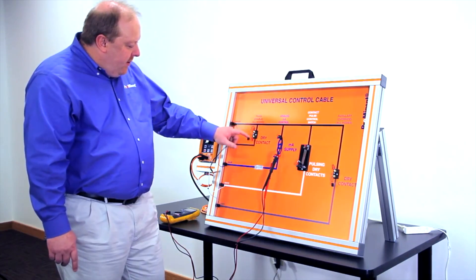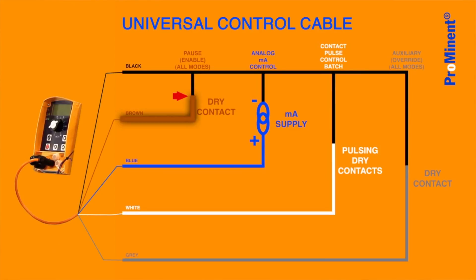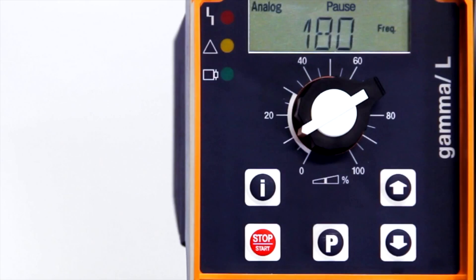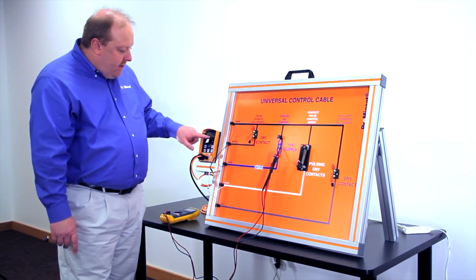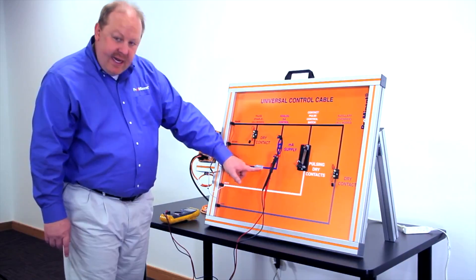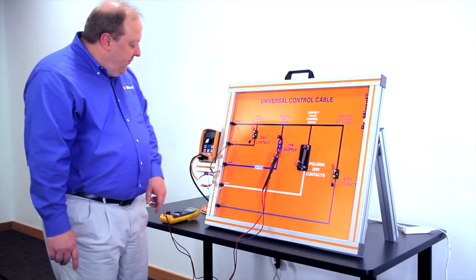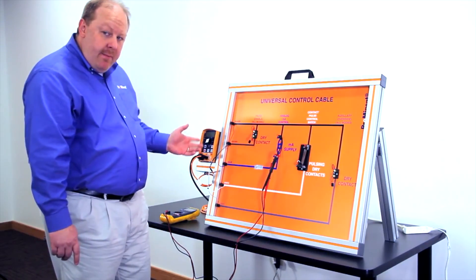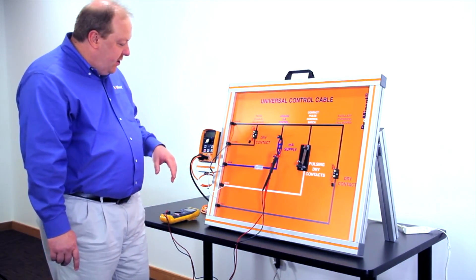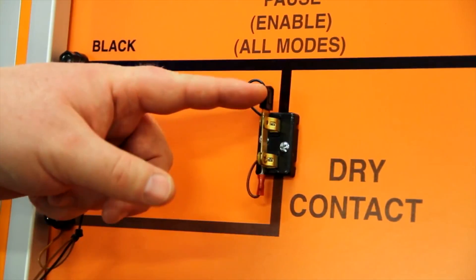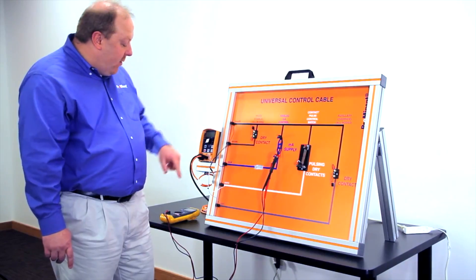If we open the contact between the brown wire and the black wire, the pump goes into a pause, but the loop is still maintained. We still see 20 milliamps through that circuit. So if we had more than one pump, we could stop one pump independent of the other pump just by opening the dry contact between the brown wire and the black wire.